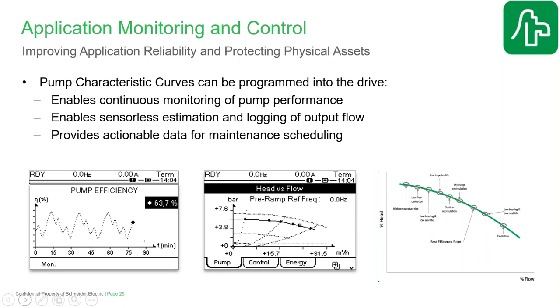Application monitoring is one of the key functions in intelligent drives today, looking at how the pump is performing. The Altivar Process drives include the ability to enter the pump characteristic curves into the drive. Those characteristic curves are the manufacturer's data on the power required to run the pump at a given speed, and what your pressure and flow output is going to be at different speeds and power usages. With that information, the drive knows how the pump should be performing. Since the drive is monitoring and controlling the application, it also knows how the pump is actually performing, and can compare the two, and then you get a direct measurement of the pump efficiency.